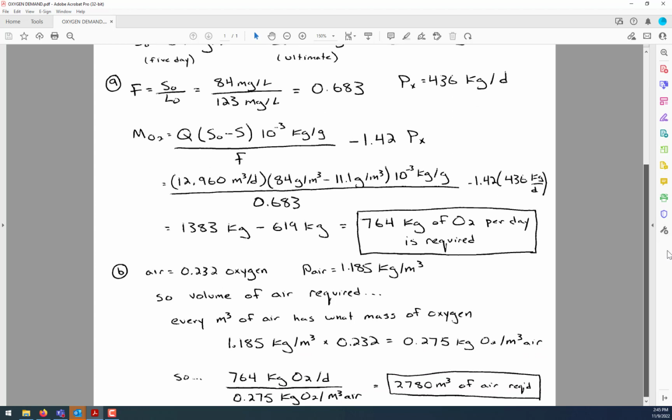So obviously the difference between those two figures is just that when we put an air bubble at the bottom of the tank, the majority of the oxygen that's being introduced at the bottom of the aeration basin is going to go back into the atmosphere. That bubble will get to the surface, it'll pop, and then that air is back in the atmosphere, and so only a tiny fraction of the oxygen that was introduced at the bottom of the aeration basin is actually getting into the liquid. So that's why we have to provide so much more air volume than you might expect if you just went by the mass basis.